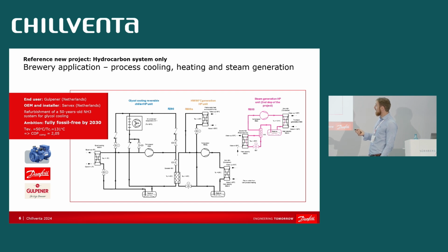Then if heating is also needed, then we send the discharge gas to the cascade heat exchanger. If heating is not needed, then we send it to the condenser, so only our refrigeration circuit works in chiller mode. If vice versa, there is no cooling required, but there is only heating, then we reverse the cycle and then air becomes a source for the second stage. Ideally, both cooling and heating will work 100%. However, life is not such. You don't necessarily need heating when you need cooling, and definitely you need to account for load balancing.